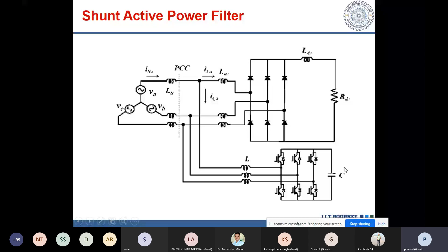You can see a sinusoidal voltage, you need sinusoidal source current. But the actual load current is non-sinusoidal. If you take the difference of the two, it is like this. Whatever is the current difference, just opposite to this current will be supplied by the filter, and therefore in that way the source current is made sinusoidal. You can also see that here this desired source current is kept in phase with the voltage. It means not only the harmonic compensation, even the reactive power compensation also takes place. So the active filter is providing the reactive power also.